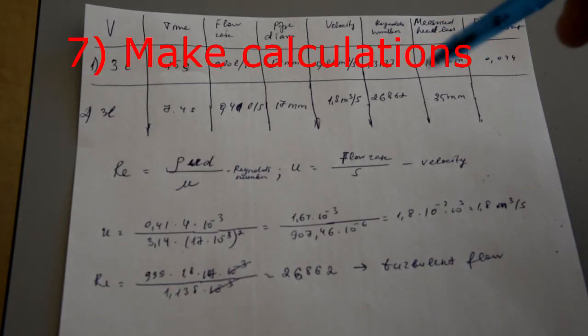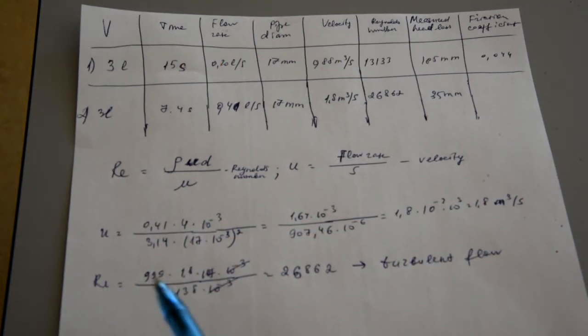Here is the example of how you have to fill the table and make your calculations using the formulas in the instruction manual. Here we have Reynolds number, and this number means that our flow is turbulent.